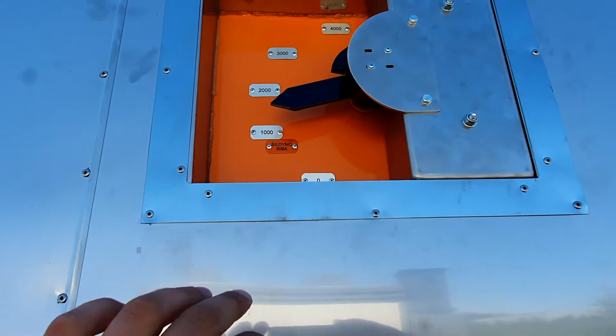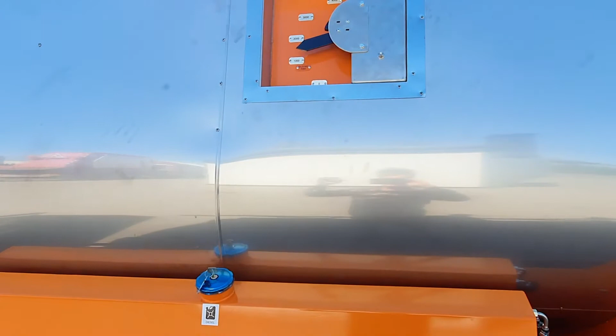If you ever have problems with the burner not starting, check if you have enough emulsion in the tank. This is one of the biggest mistakes our operators make. We get many phone calls about the burner not working, and since there is almost no emulsion in the system, we cannot allow the burner to start because it may be a risk of fire, since the emulsion is not covering the full heating system.